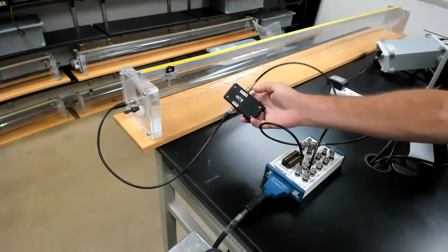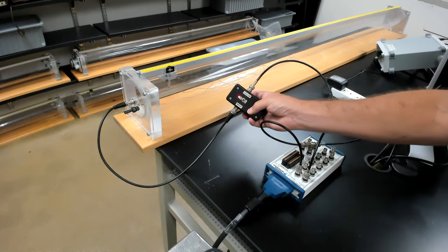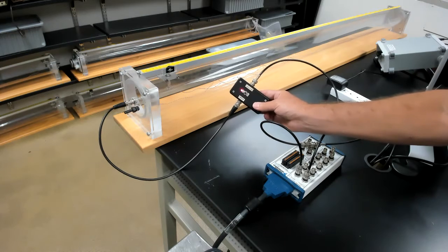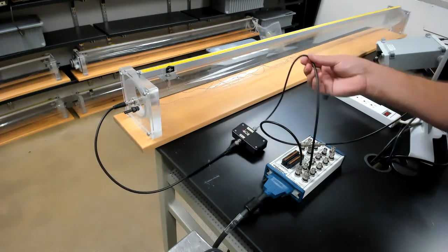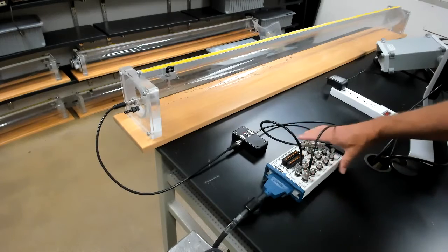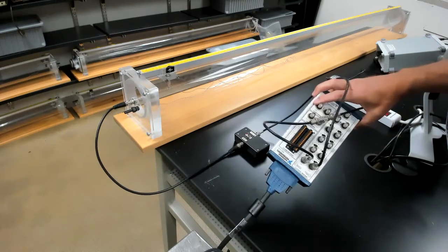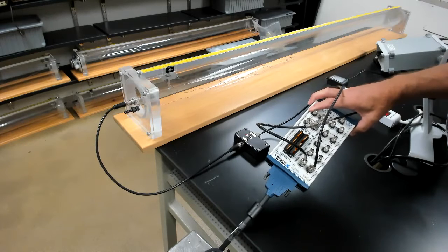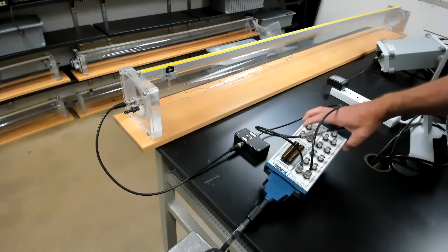So for that purpose, we have an audio amplifier. I'll turn it on here. And this is just a times 100 amplifier that boosts the signal to a more measurable range. And the signal is then coupled into the analog to digital converter for the computer. By the way, this box is not the analog to digital converter itself. That's a card that's mounted now on the computer chassis. This is just a convenient breakout box so we can easily connect things to it.